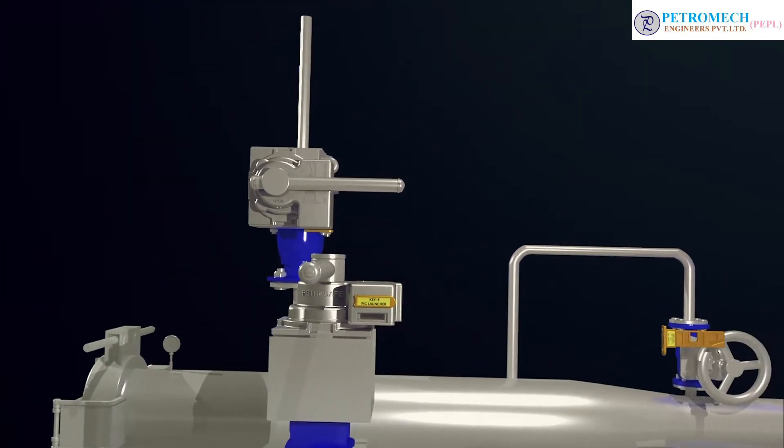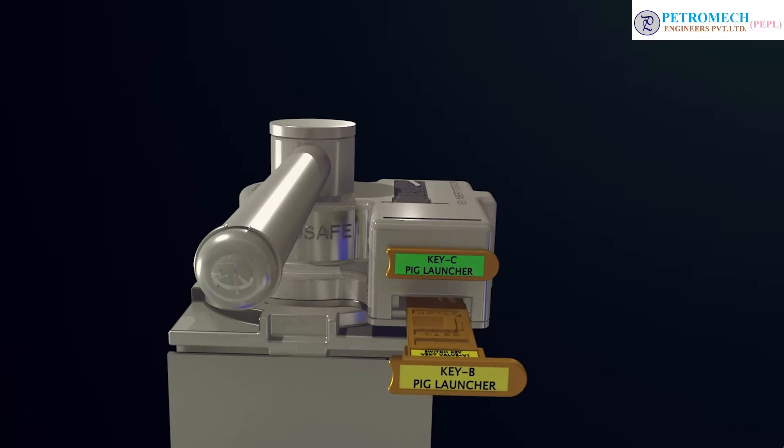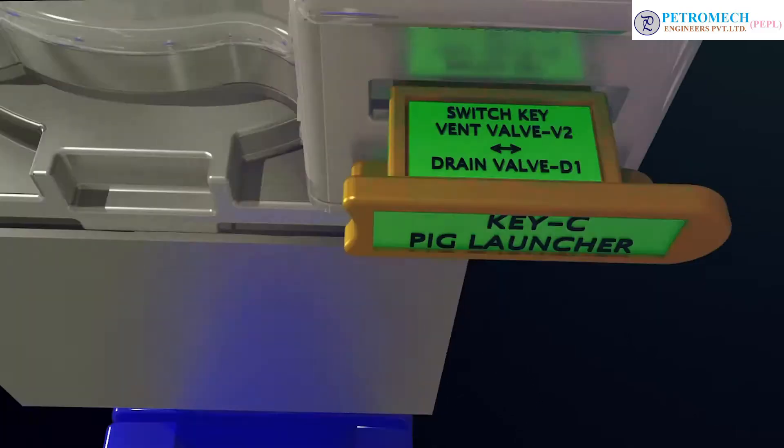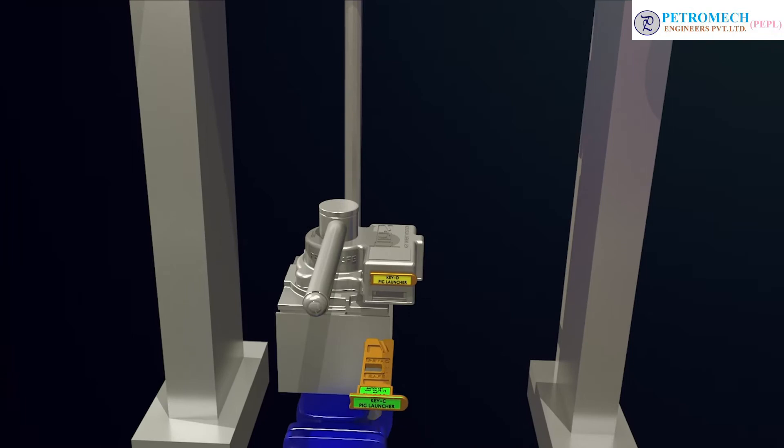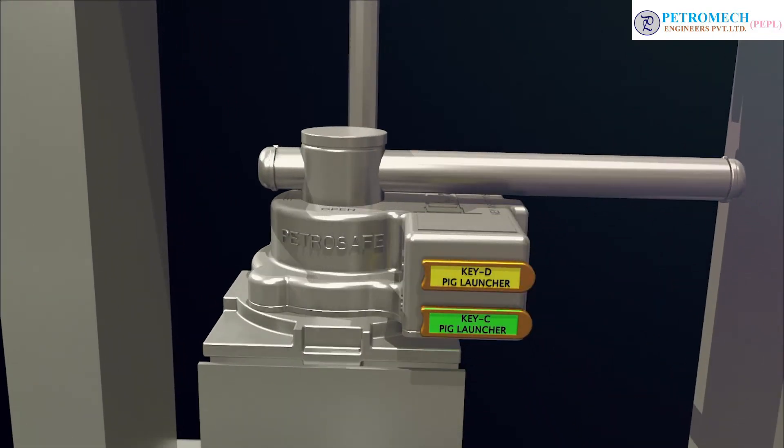Step 3: Insert key B into vent valve V2. Open the valve and release key C. Step 4: Insert key C into drain valve D1. Open the valve and release key D.